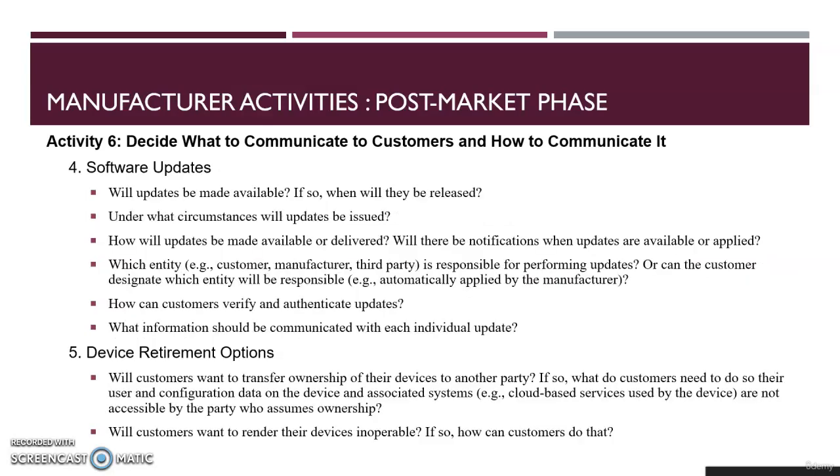Next and last we are talking about is device updates. Will updates be made available? If so, when will they be released? Under what circumstances will updates be issued? How will updates be made available or delivered? Will customers be notified when updates are available? How can customers verify and authenticate updates? What information should be communicated to each individual about the updates?